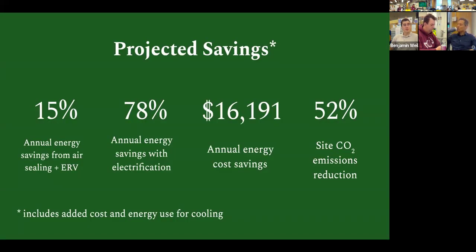So this shows the projected savings that we would get from this new system upgrade. This also includes the additional cost that we would incur from adding cooling, because obviously that would bump up your electricity use a bit. And these numbers were calculated based on local weather data and a regression model based on the equipment that we mentioned. So it's about a 15% savings if we were to only do some of those envelope upgrades, as well as adding the rooftop units. And then with the air to water heat pumps, that's about 80% savings. So that's with almost full electrification. It comes out to about $16,000 a year and a 50% reduction approximately in CO2 emissions.